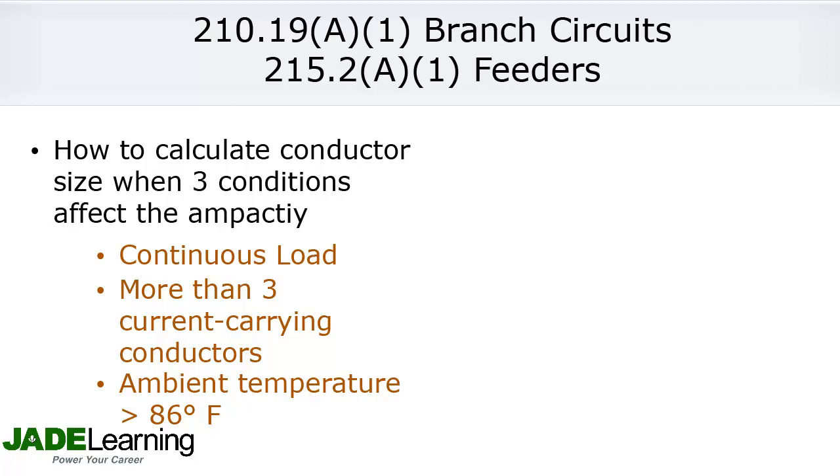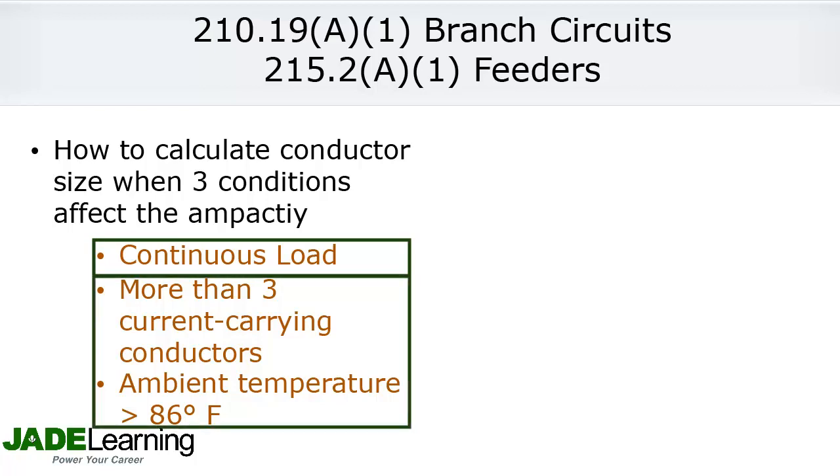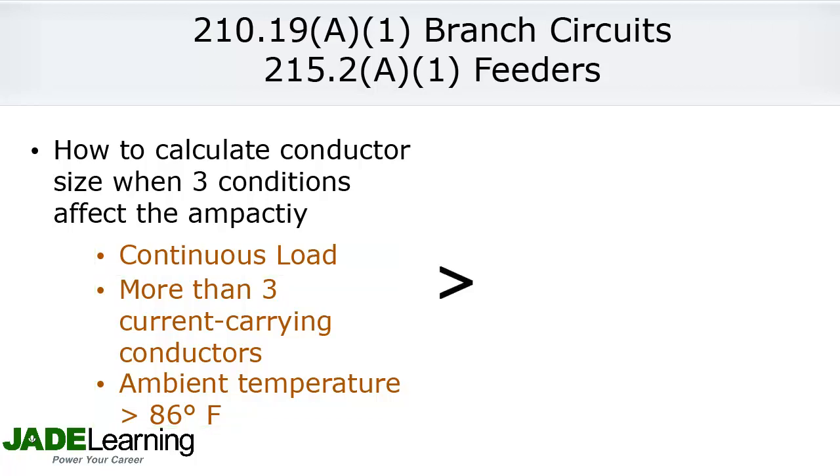The 2014 NEC says that we compare the size of the wire we get for the continuous load on the one hand with the size of the conductor to allow for more than three current-carrying conductors in conduit and an ambient temperature greater than 86 degrees Fahrenheit on the other hand, and we select the larger of the two sizes.